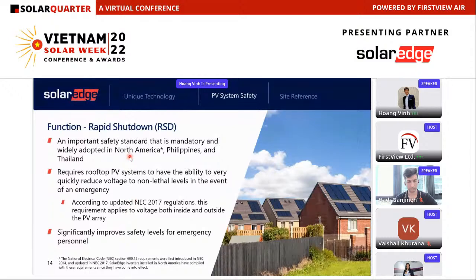So it is very important to have rapid shutdown to protect the PV system. Rapid shutdown is very important. The standard is now mandatory, adopted firstly in North America and now in Asian countries such as the Philippines and now in Thailand. They are applying rapid shutdown to protect their PV systems for safety. Rapid shutdown requires the rooftop system to have the ability to very quickly reduce the voltage to non-lethal levels in the event of an emergency. According to the update of the NEC 2017 regulation in America, this requirement applies to the voltage both inside and outside of the PV array. And this revision significantly improves the safety level for emergency personnel.